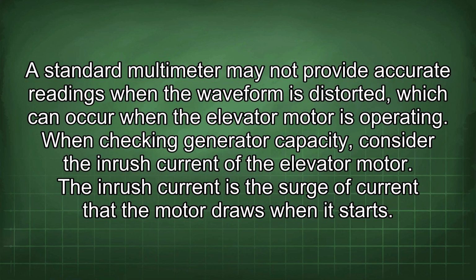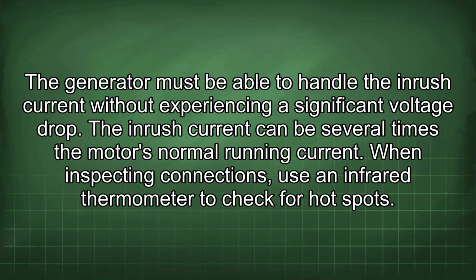When checking generator capacity, consider the inrush current of the elevator motor. The inrush current is the surge of current that the motor draws when it starts. The generator must be able to handle the inrush current without experiencing a significant voltage drop. The inrush current can be several times the motor's normal running current.